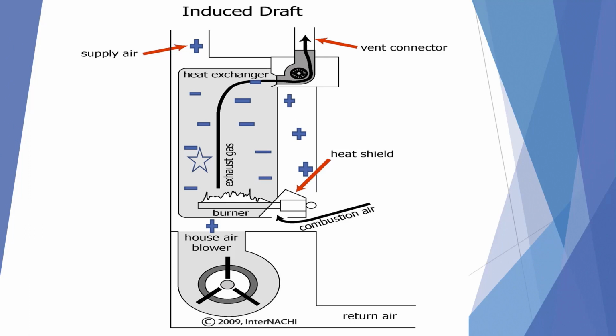There have been many tests done over the years showing that if a hole is developed on a heat exchanger, because of the positive pressure that is around the heat exchanger and the negative pressure that is produced inside the heat exchanger by the induced draft motor, any products of combustion are going to remain in the heat exchanger and will go out through the vent and not into the conditioned air space.